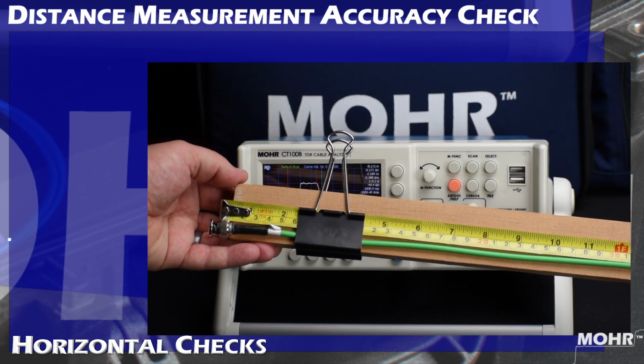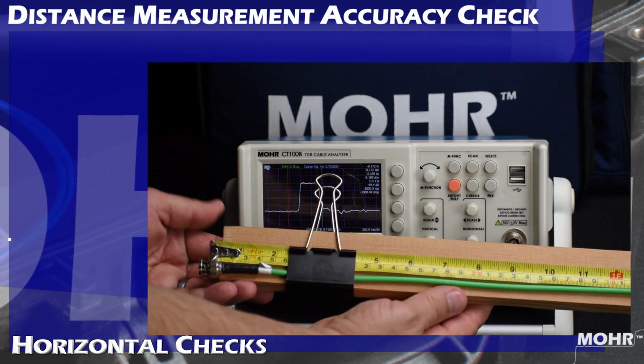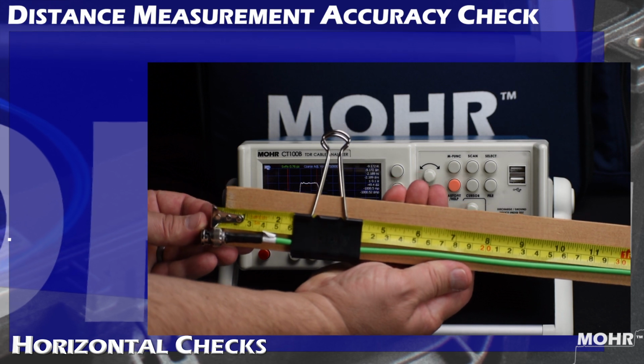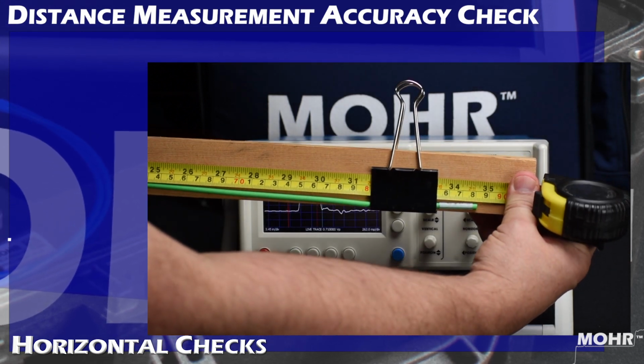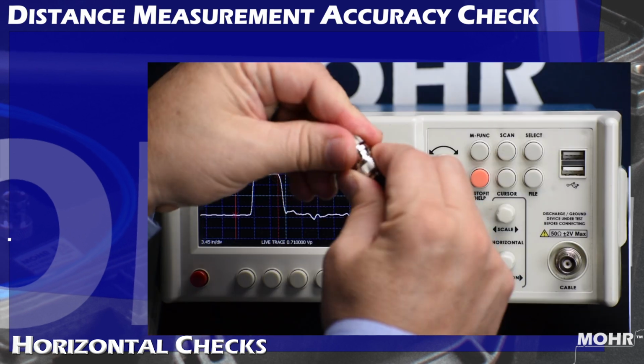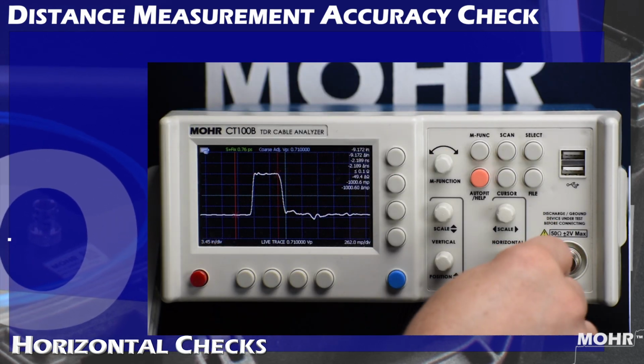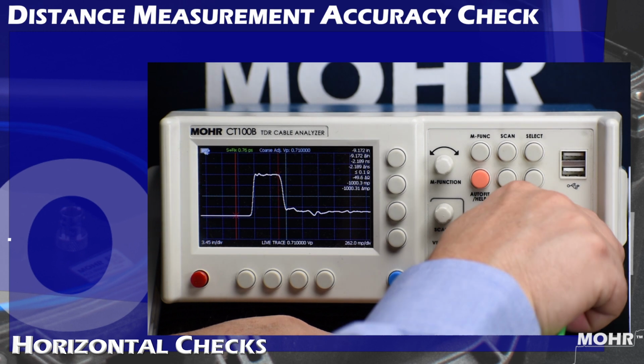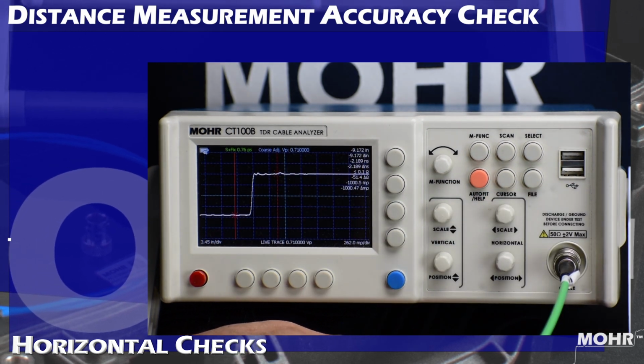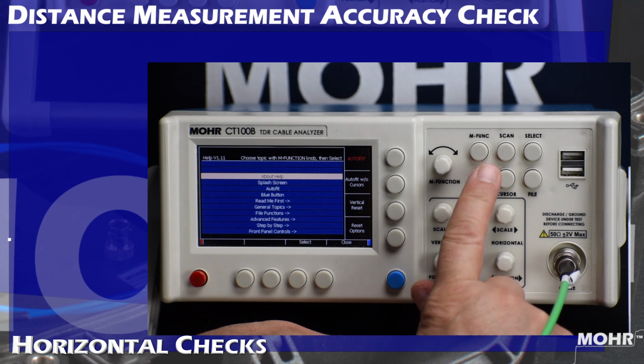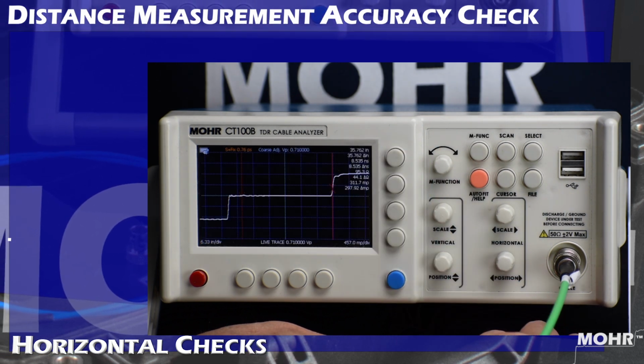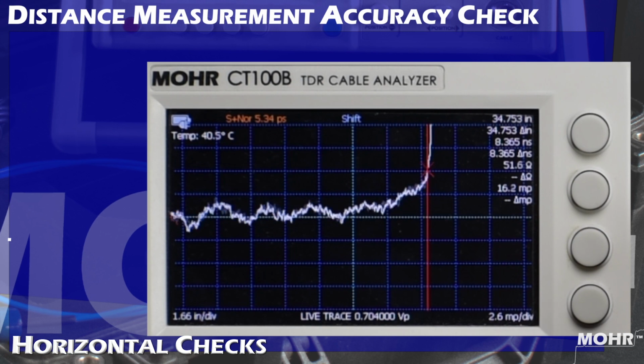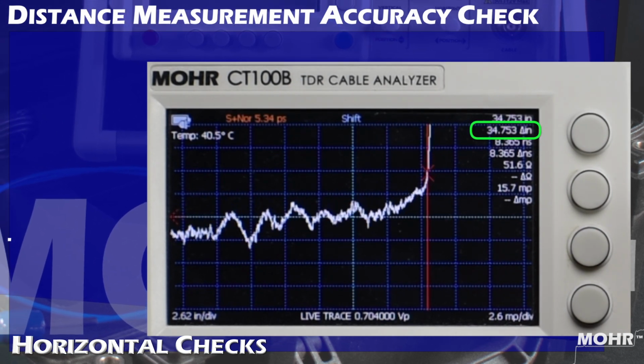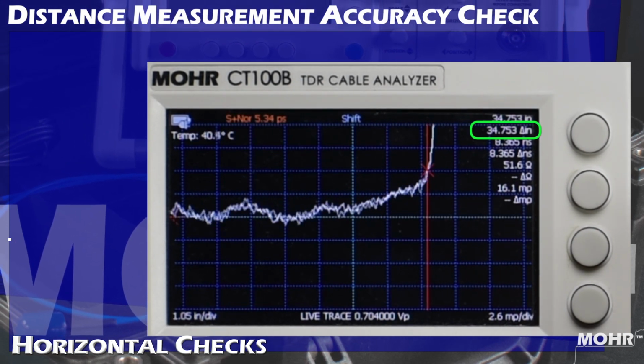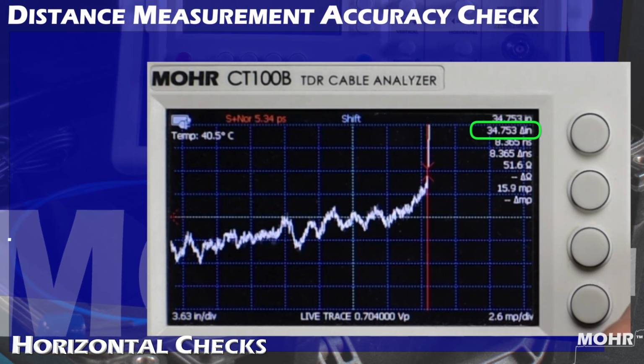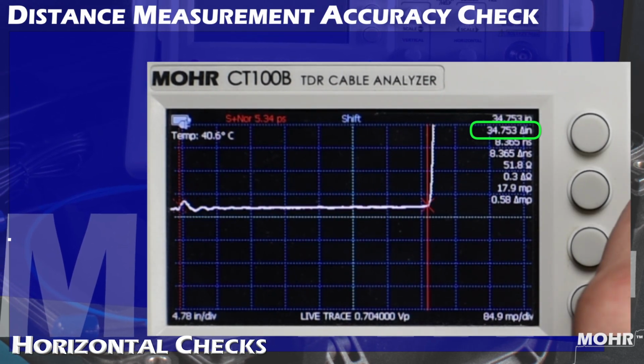For the distance measurement accuracy check, in a previous video, I measured this cable to be 34.75 inches and having a VP of 0.704. We will do that test again and compare the results. Accuracy is determined by taking a cable of known length and velocity and comparing the known values against measured values. Accuracy is reported as a percentage when determining accuracy. This is to ensure that horizontal calibration has been performed accurately, and accuracy should be checked for short, medium, and long settings.